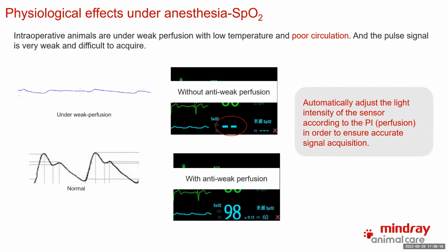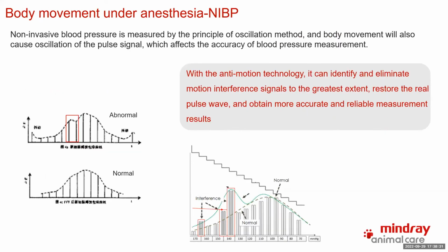So when we detect the perfusion is not good, we can automatically adjust the light intensity to get accurate SpO2 readings. So that's for the SpO2.